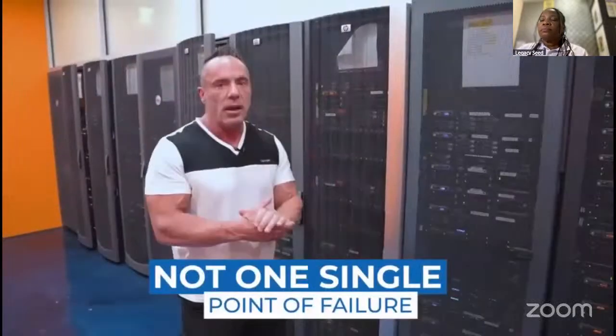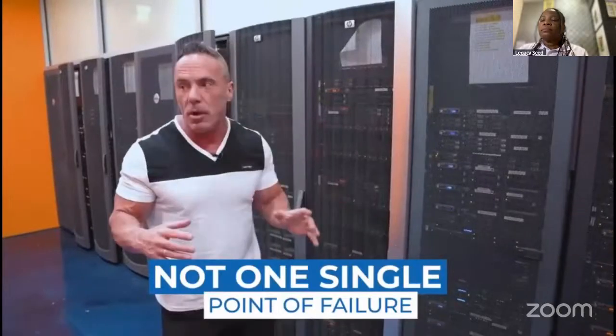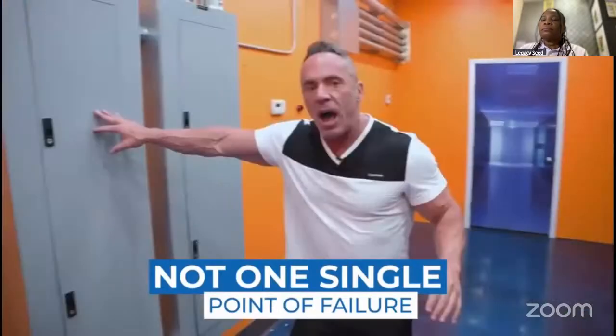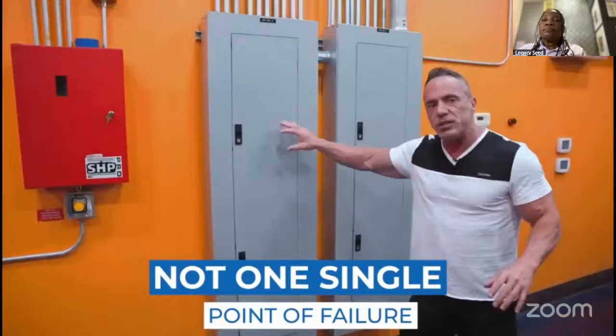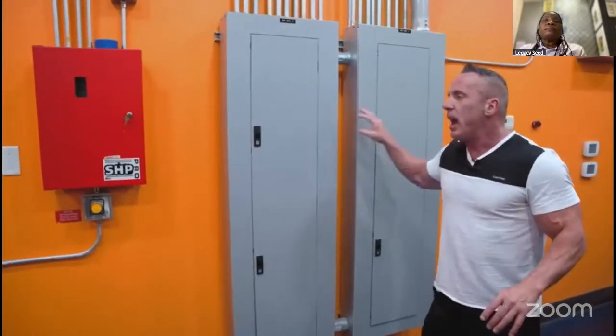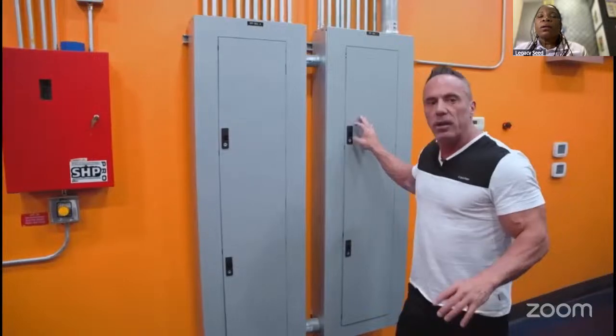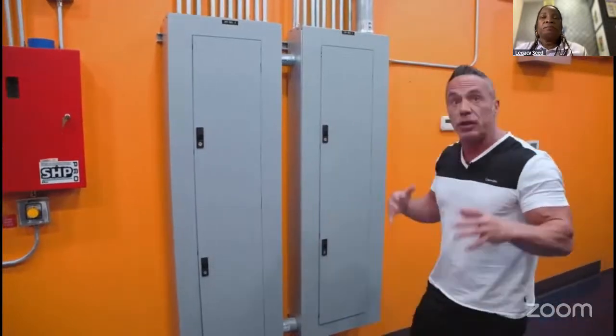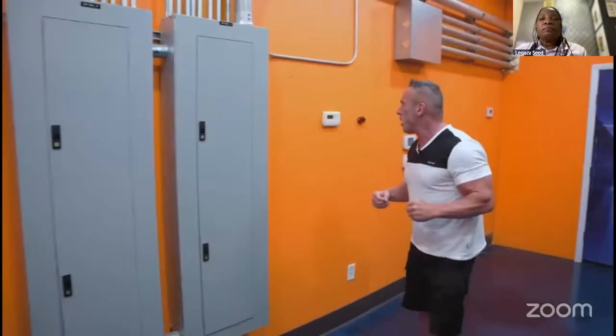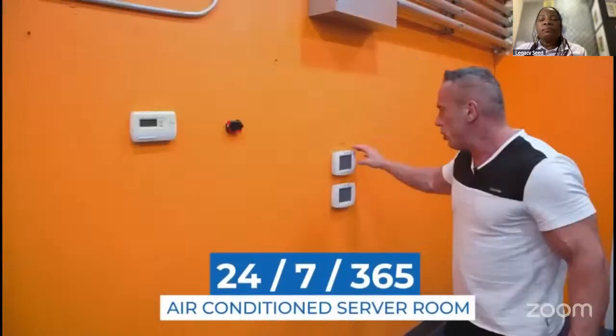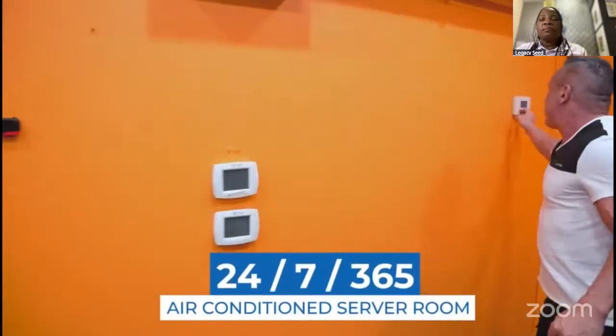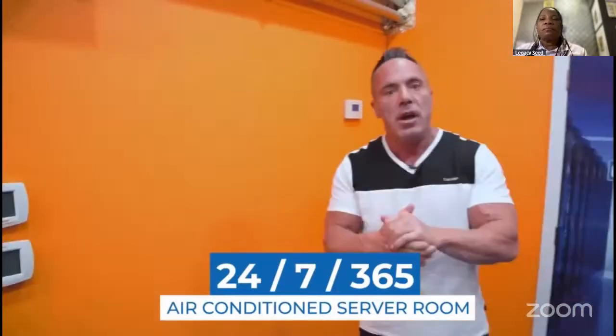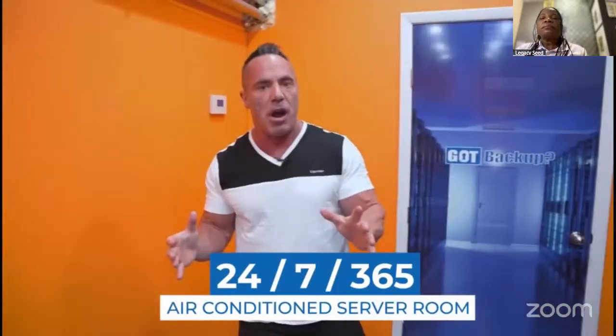There's also no single point of failure in the server room. As an example, there's A power and B power. Every server is plugged into A power, every server is plugged into B power. Also, relative to cooling of this room, if you come over here, you'll see we have 1, 2, 3, 4 air conditioners in this server room. So the air is never going to be a problem.